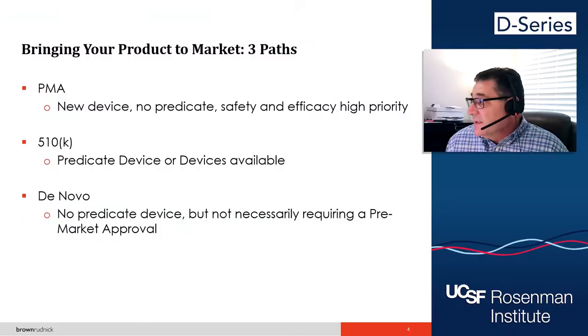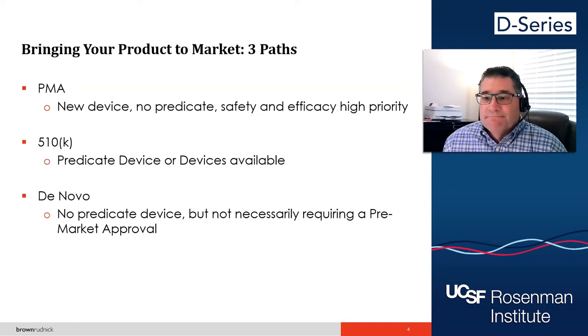So as we move to the next slide, there are three ways. You need a pre-market authorization or approval, generally referred to as a PMA in the parlance of this, in the jargon of the industry. And that's going to be a new device. You don't have something called a predicate device.